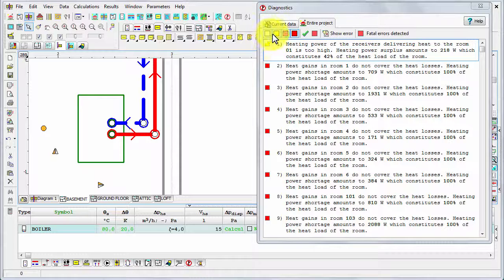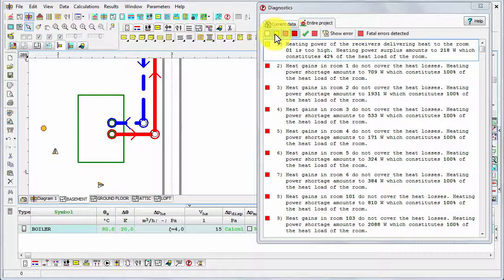Then you've got yellow message, as you can see for example here. It's a warning. It's already something not OK and the program wishes to warn you, but it's nothing serious yet. For example, here we have the surplus of the heating power. Most probably the heating load in this room was very low. Remember we had more radiators in one room. And then the program selected the smallest radiator, but it's still too big. But it's not very important and you may decide whether to correct it or not.